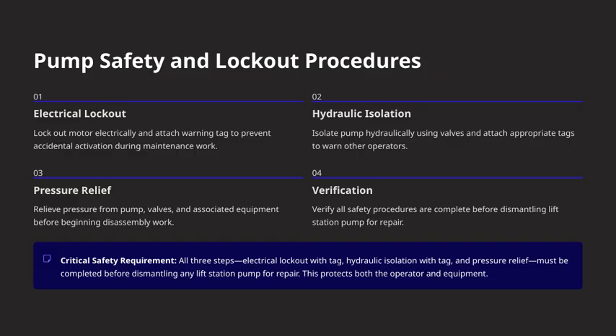First, electrical lockout is crucial. You need to lock out the motor electrically and attach a warning tag. This step prevents accidental activation while you're working on the pump. Next, hydraulic isolation involves isolating the pump hydraulically using valves, and it's equally important to attach the appropriate warning tags. These tags alert other operators that maintenance is in progress and that the system is isolated.